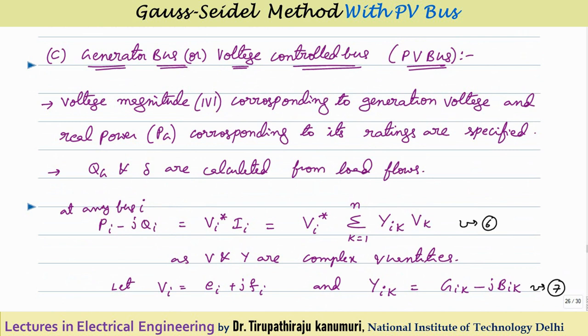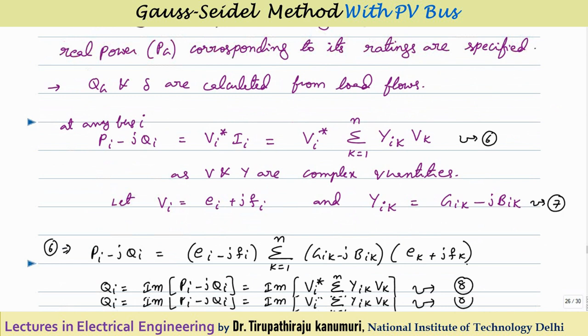Now let us discuss the PV bus in detail. For a generator bus or voltage control bus, the active power and voltage magnitude are given. The voltage depends on the field circuit (reactive power control) and the active power depends on the mechanical/governor input. That is why P and V are specified, and the remaining two parameters - the voltage angle delta and the reactive power QG - must be calculated from the load flow analysis.